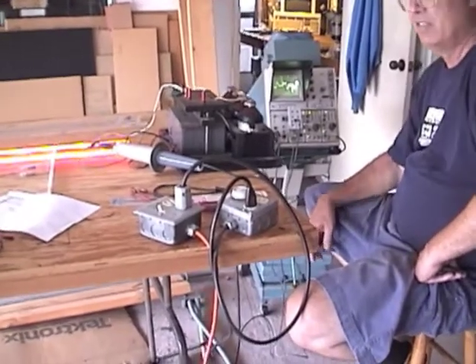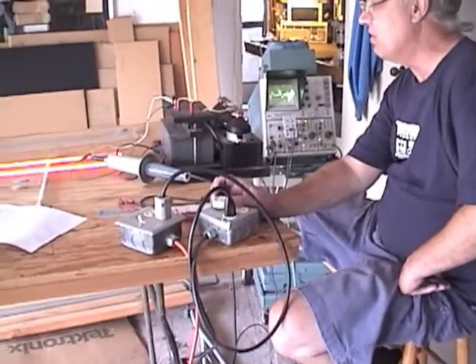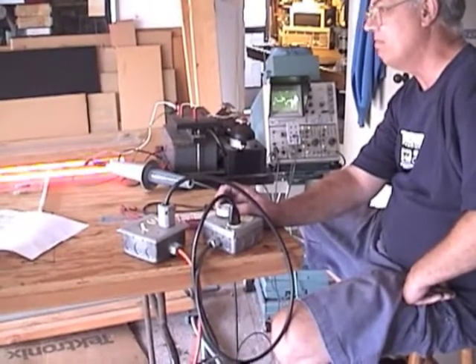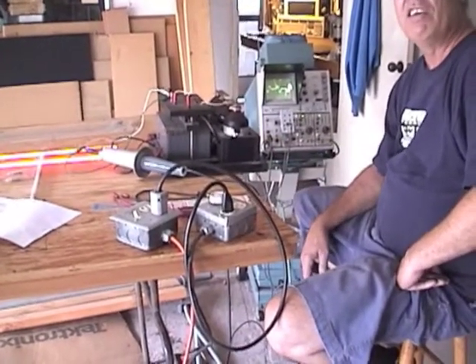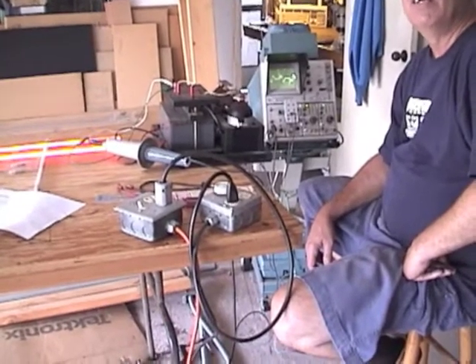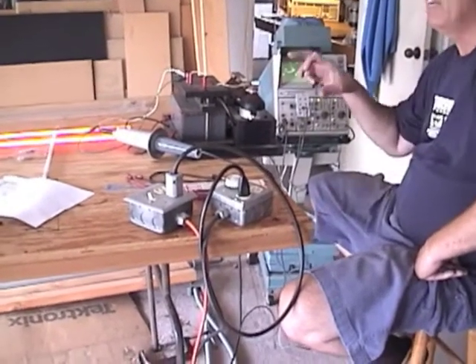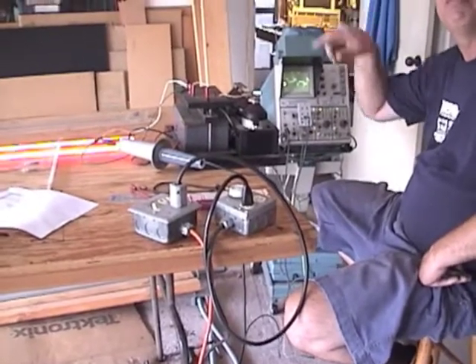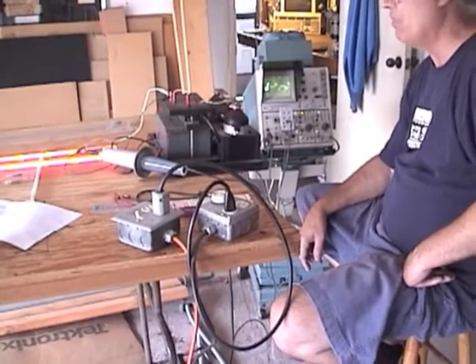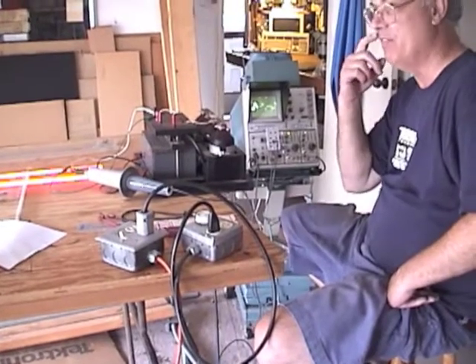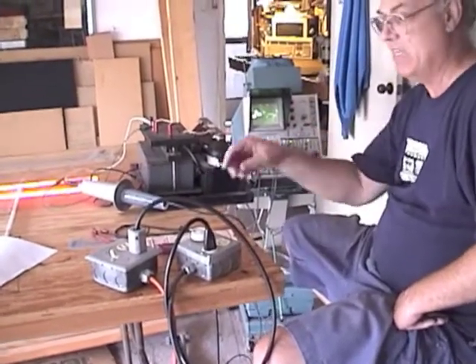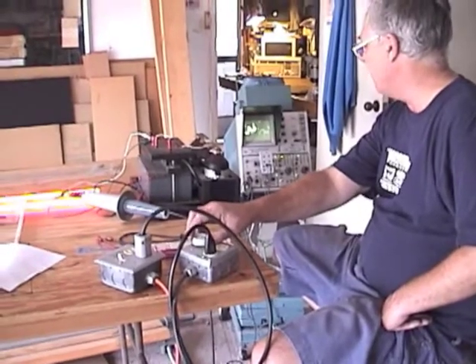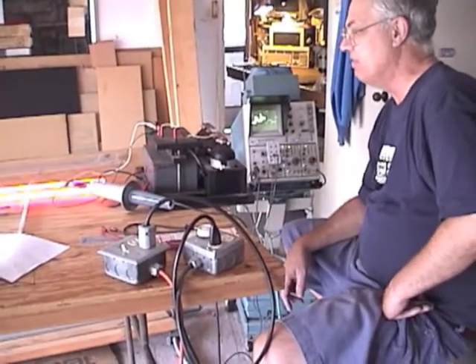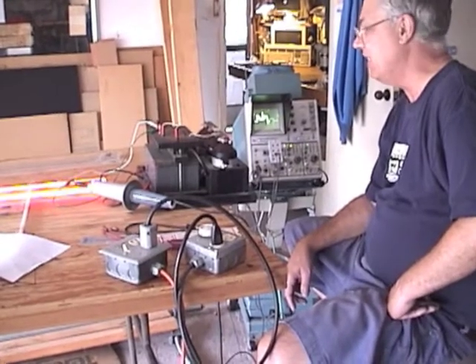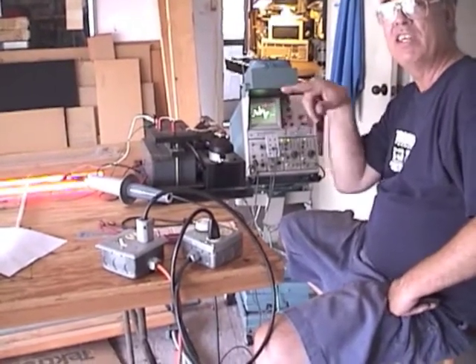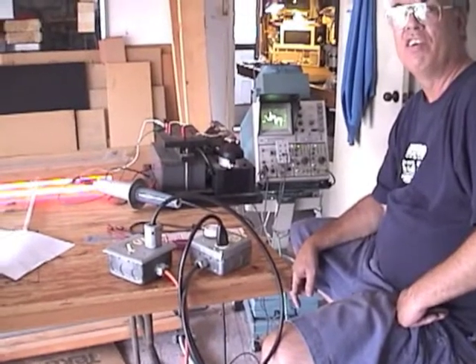Because you're going to have to change the transformer, right? Well, typically what most people do when they're running glass work with a dimmer is underloading the tranny anyhow. So by having less glass on the tranny, they're covering that voltage spike problem. If you're running a full load on a tranny, especially if I was dimming a 15 with a full load on it, you get some nasty voltage spikes at partial load. And it's not the load on the tranny that's going to kill it, it's those stupid voltage spikes sitting there punching at the insulation inside the tranny, trying to arc over.